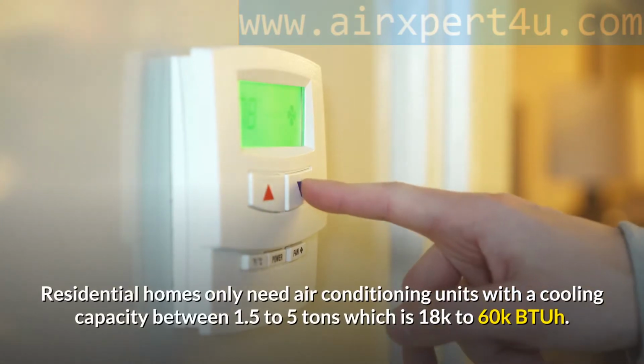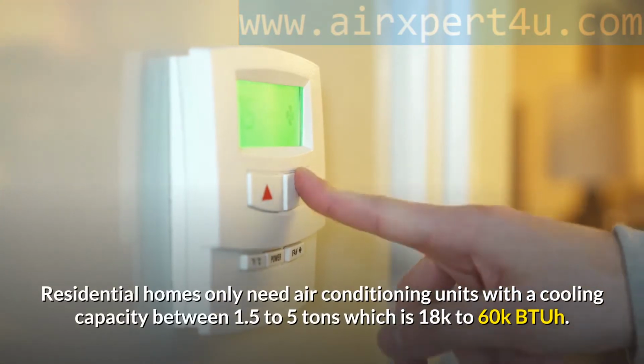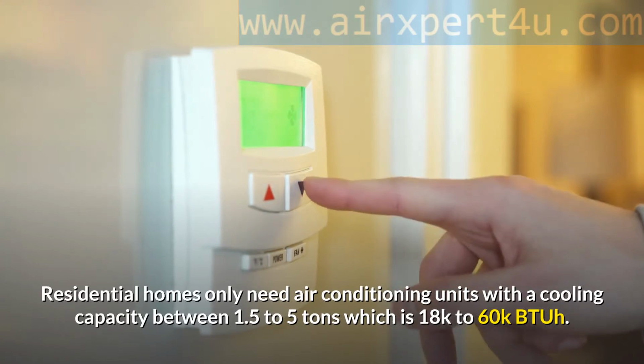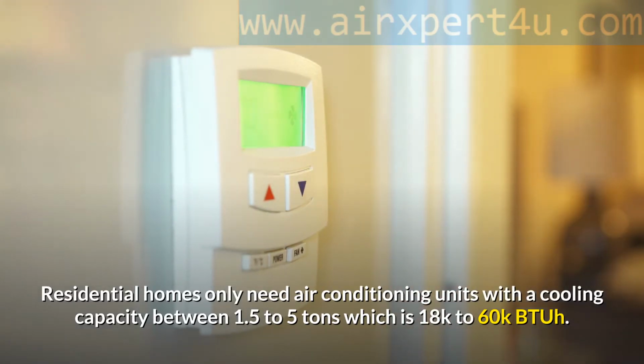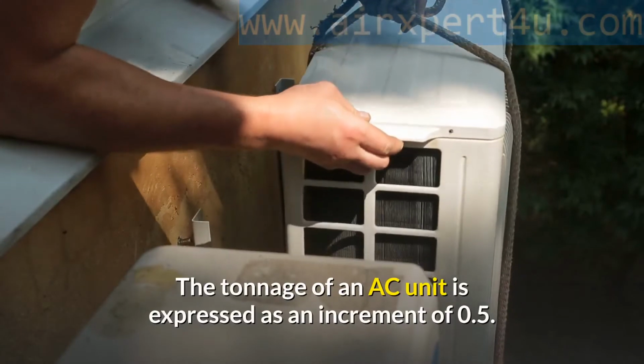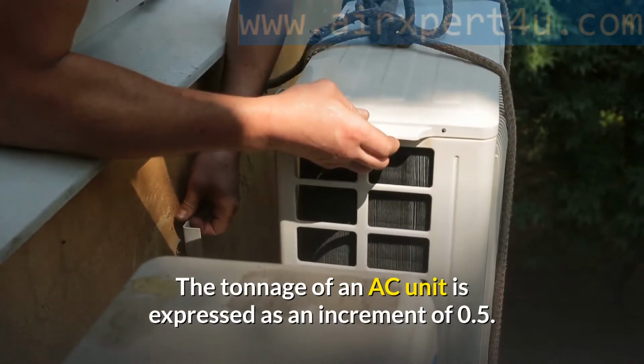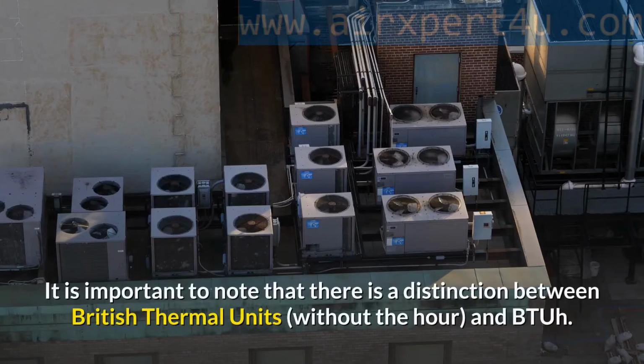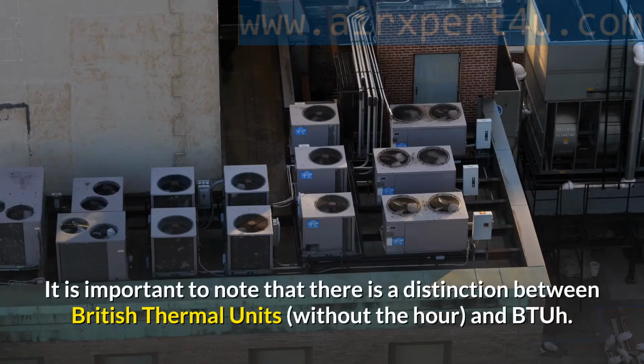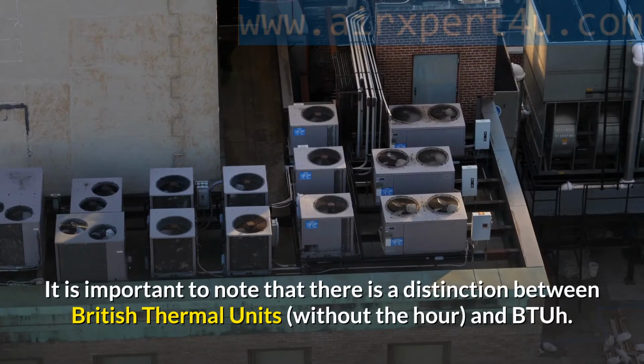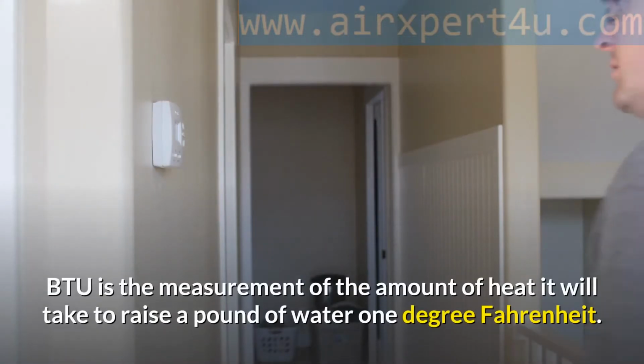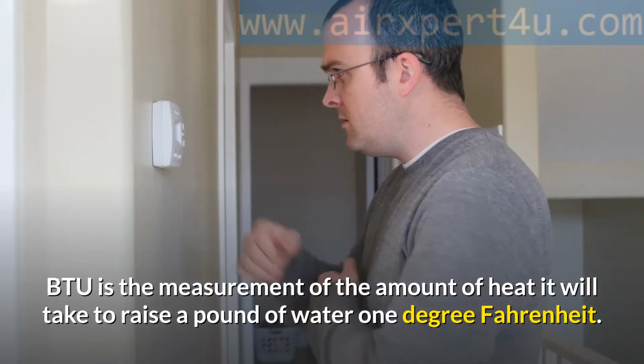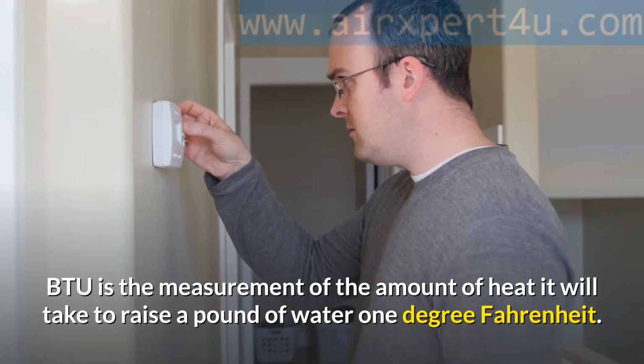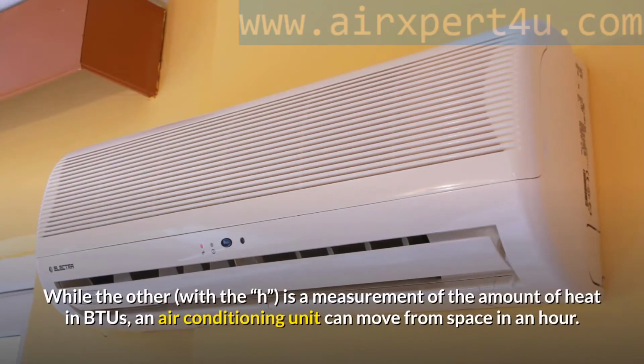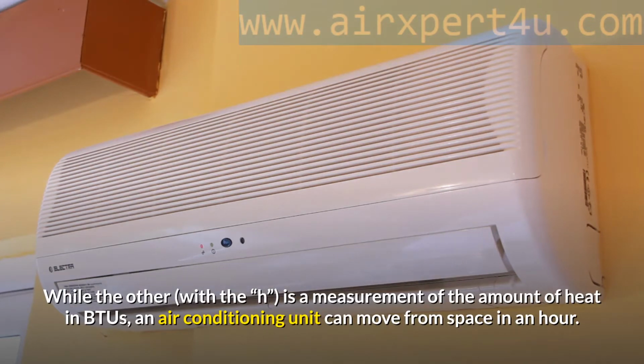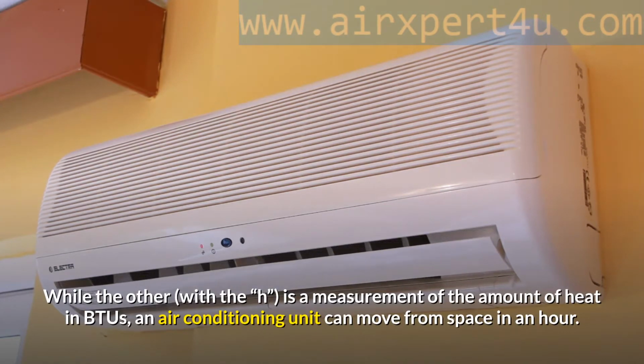Residential homes only need air conditioning units with a cooling capacity between 1.5 to 5 tons, which is 18K to 60K BTUH. The tonnage of an AC unit is expressed as an increment of 0.5. It is important to note that there is a distinction between British thermal units without the hour and BTUH. BTU is the measurement of the amount of heat it will take to raise a pound of water 1 degree Fahrenheit. While the other, with the H, is a measurement of the amount of heat in BTUs an air conditioning unit can move from a space in an hour.